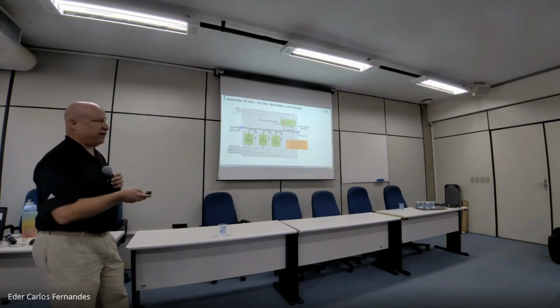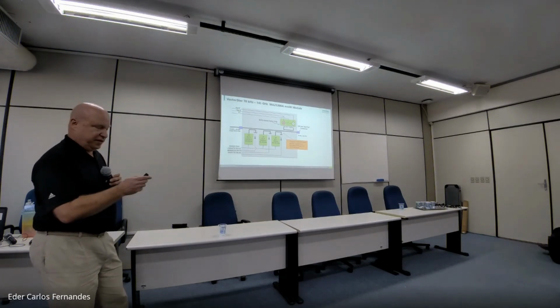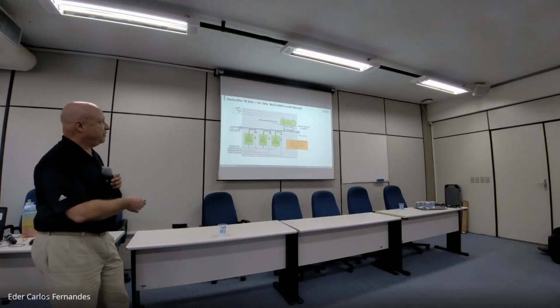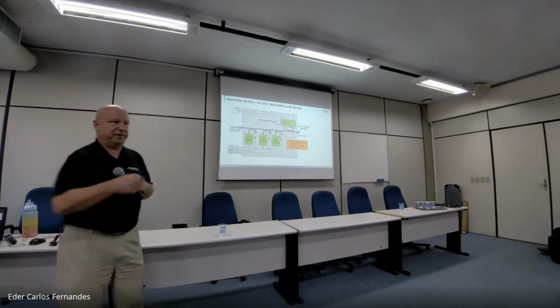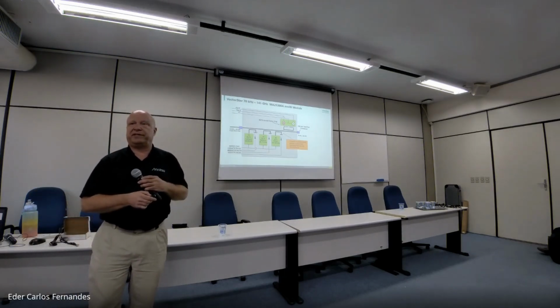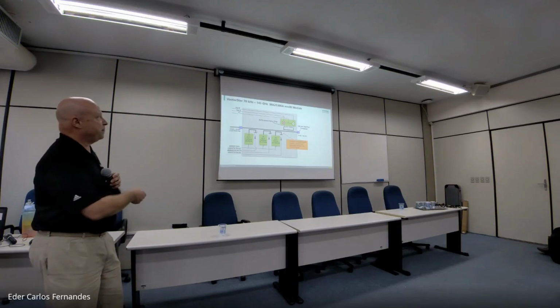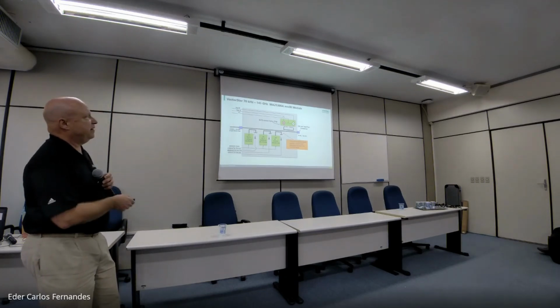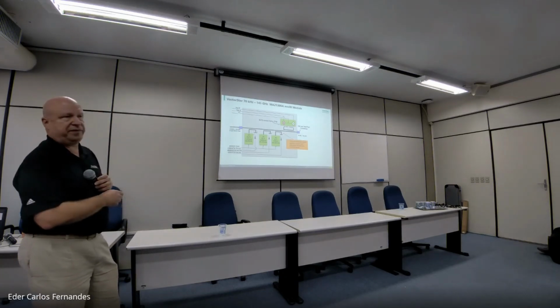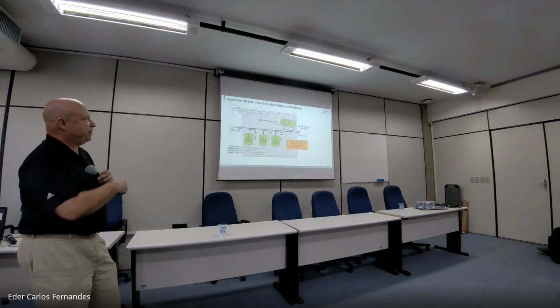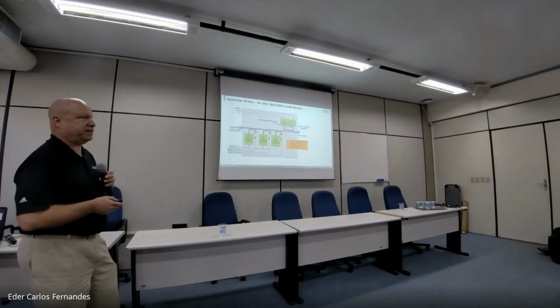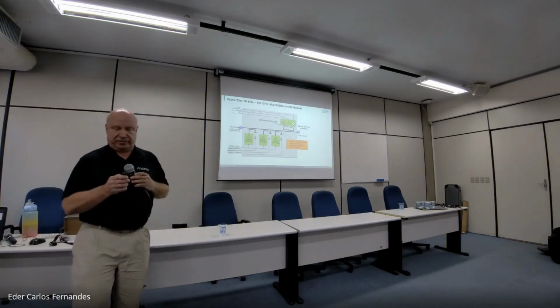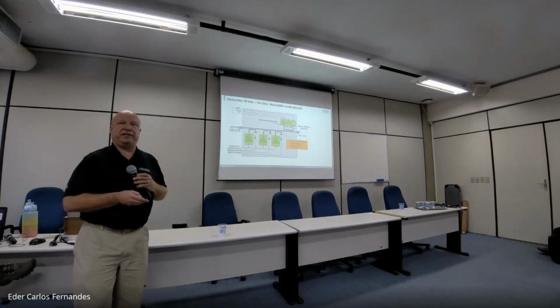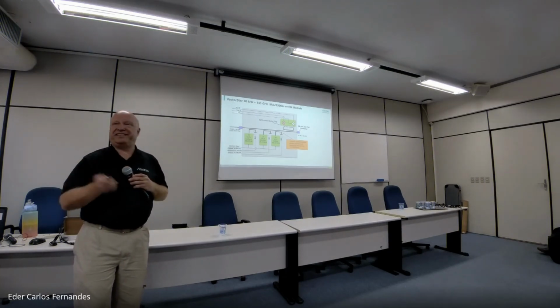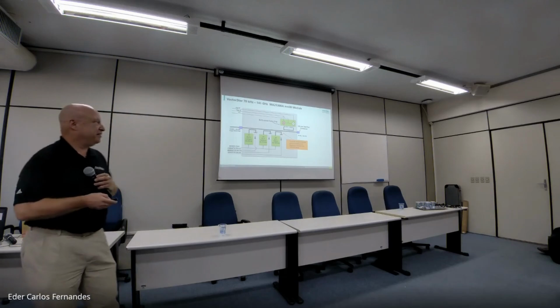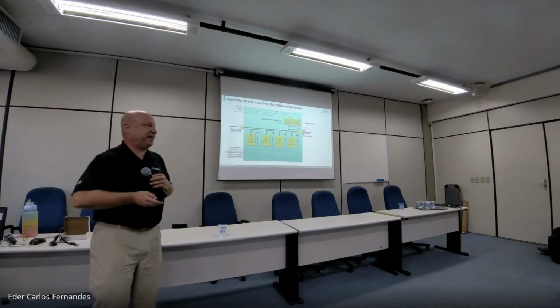Shifting to the 145 gigahertz module, the first thing you notice is that instead of 2 multipliers, now there's a third one because we're going up to 145 gigahertz. The receiver can cover the full range up to 145 as well. Now the test port connector is a 0.8 millimeter as opposed to the 1 millimeter, but basically the same interconnects exist in this module. What happens when I go to 220? Anybody want to guess? I need one more multiplier, exactly.